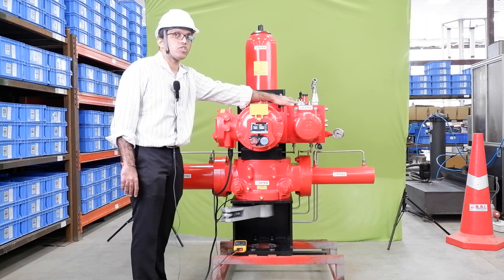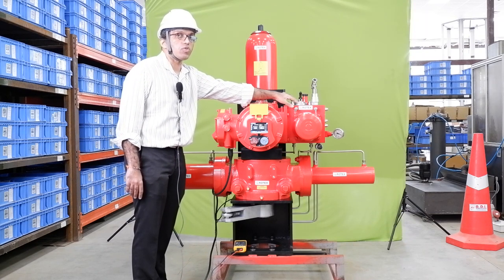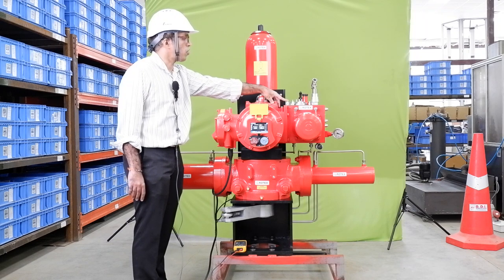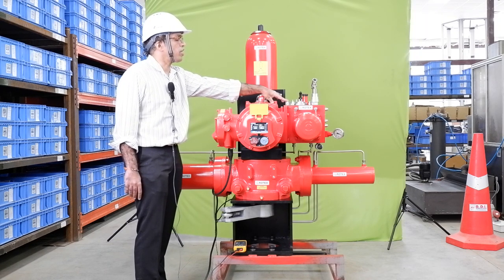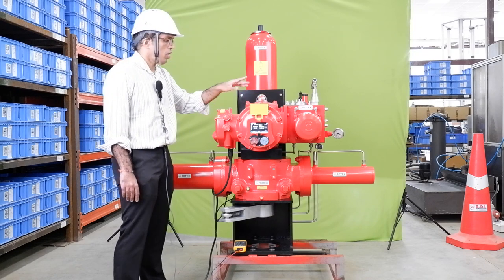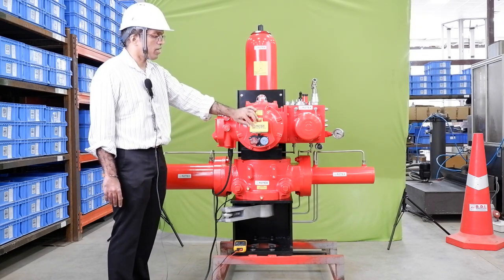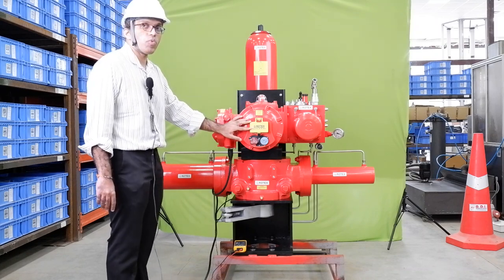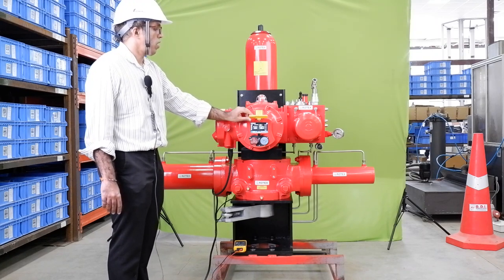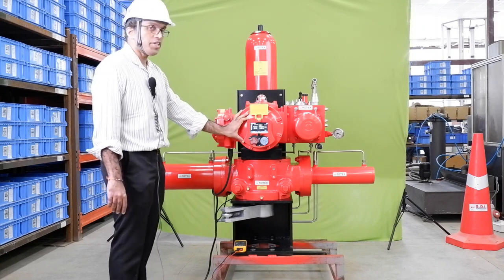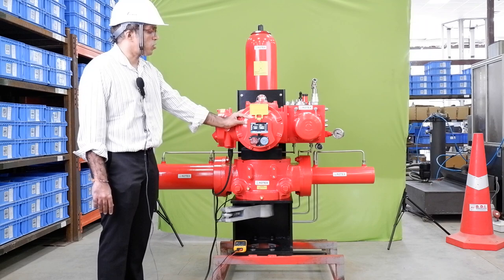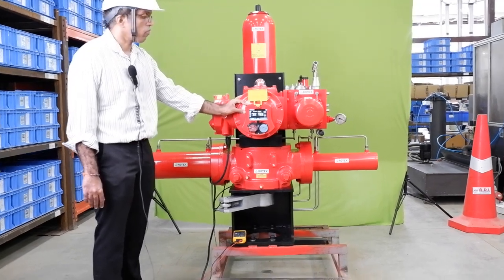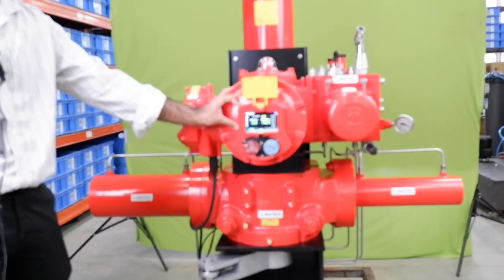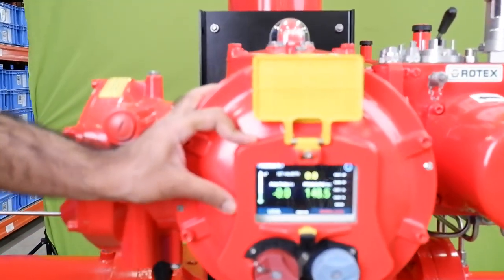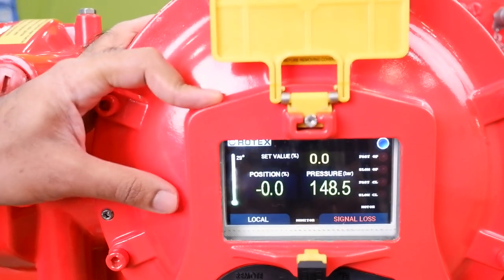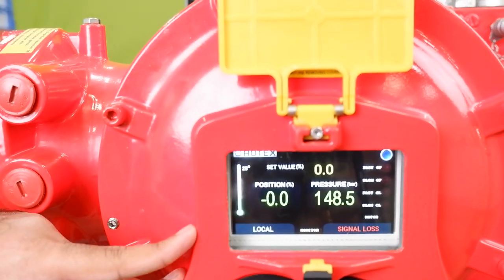We have a mechanical selector switch to manually open and close the valve, and we have flow control valves to vary the speed of open and close operation. The EHF head has an LCD cover which protects from UV, from the sun. The EHF head has this LCD that displays all the process values, all the alarm indications, all the SOV indications, the open-close indications, and the different modes of operation.